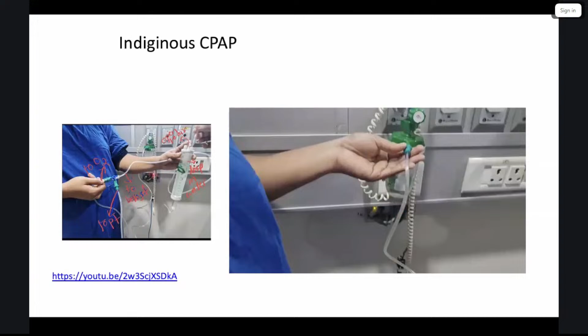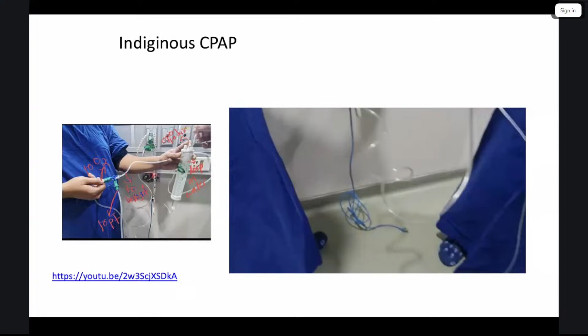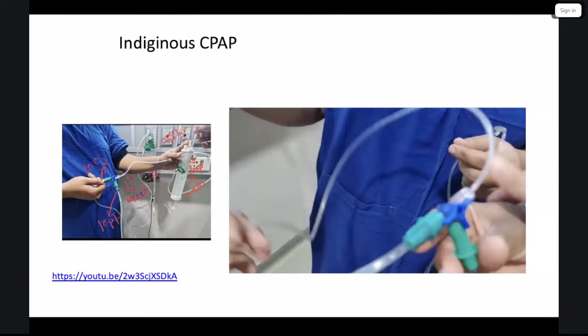This is an indigenous CPAP setup. This slide shows a simple and affordable CPAP system. It is made using basic medical items like an oxygen source, tubing, and a water bottle. This system is called bubble CPAP. Air passes through water and creates bubbles. These bubbles generate pressure. The pressure keeps the preterm baby's lungs open and helps in breathing. This image shows how the system is set up and how the bubbling works. This practice is still continued in a lot of centers, even in Mumbai, as a makeshift CPAP.